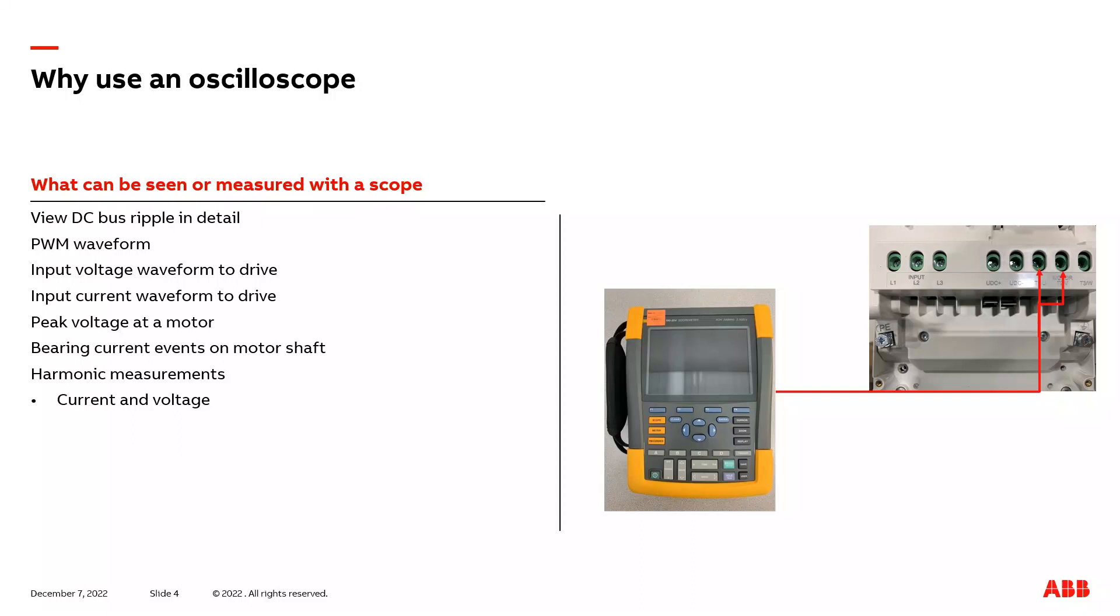If we take a scope and apply it at the motor, we can look at the peak voltage at the motor terminals and see if it is too excessive to determine if maybe we need an output drive filter. Or we can also take the scope and apply it between the motor frame and motor shaft to determine if we have any bearing current problems. We would be looking for a quick rise in voltage and a quick drop when we take a measurement between the motor frame and motor shaft for bearing currents. And then for some higher end scopes, they have the ability to measure input current and voltage harmonics.